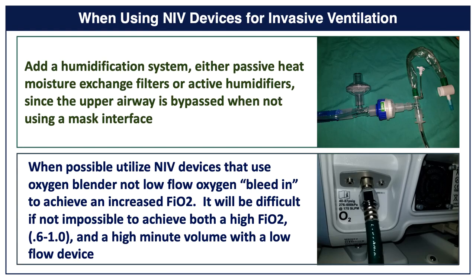With these, normally you would have some humidity from your upper airway if you're utilizing a mask, although a lot of us now utilize humidifiers on our mask devices. But if you're bypassing that and utilizing an ET tube, you definitely need some way to maintain your moisture. One option would be a heat moisture exchanger, which also allows you to have another filter there.